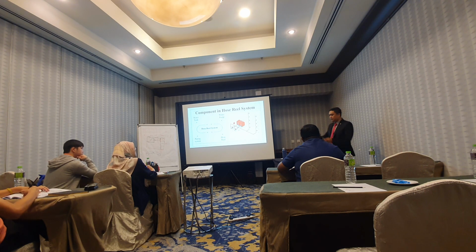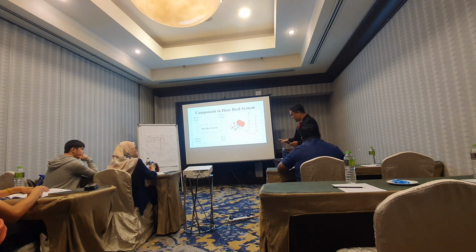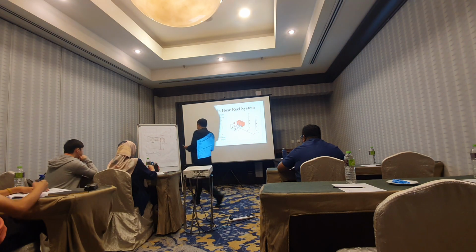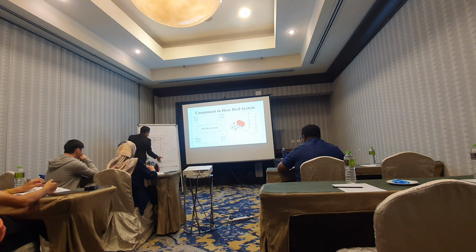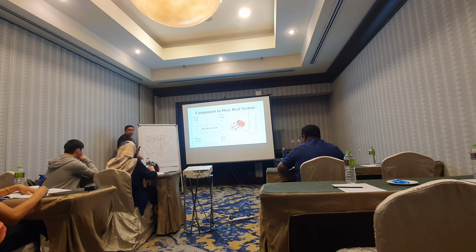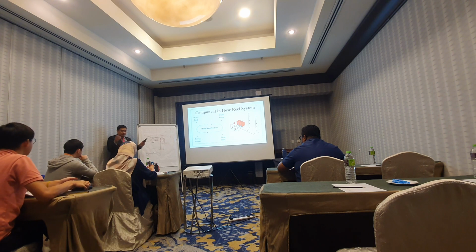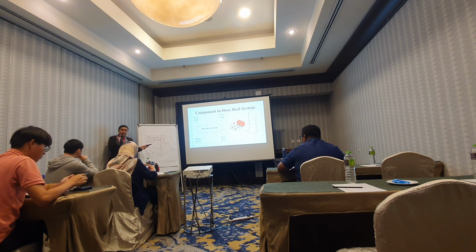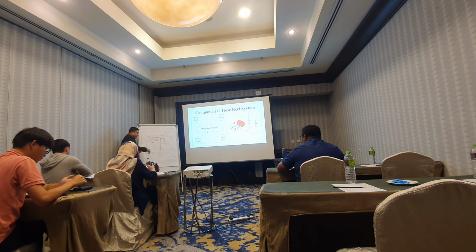So whenever you see a drawing, the fire department approval ticks on the drawing, at the lowest part of the drawing, there must be a code being used. They will put it beside the drawing like this, at the edge. Usually you will see them tick the drawing. Of course Malaysian standard is there. But you have to check: for a very large shopping mall, normally it does not comply with MS. Sometimes it uses NFPA. When they design with NFPA, if they tick NFPA, you go for UL FM.